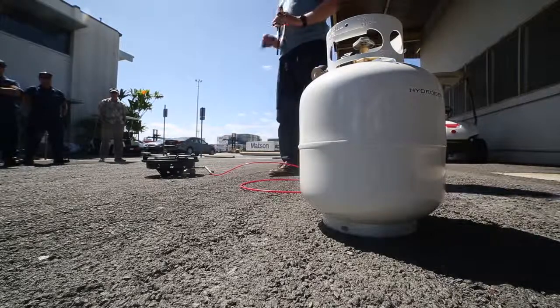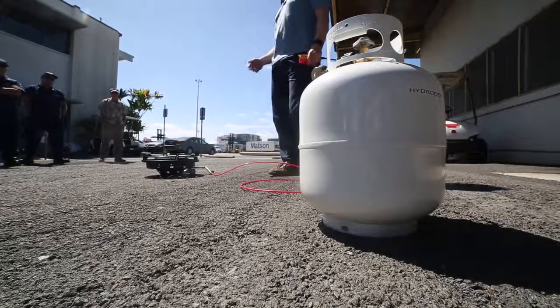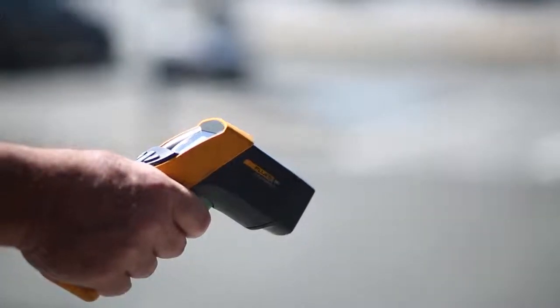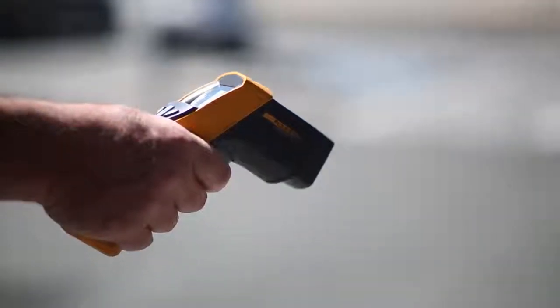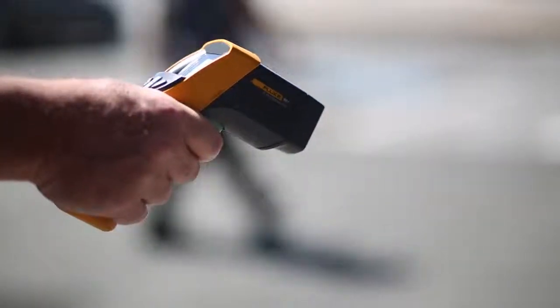You can see just a few little flecks of color, and that's mainly some impurities that are either in the line or on the burner itself. So in daylight, it's pretty hard to see. But that flame temperature, again, is about 4,000 degrees Fahrenheit, so it's really hot. Very little radiant heat, though, so if there's a jet of it, you can get very close to that, which can be a hazard. You know, there's not a lot of anything to indicate that you're getting into a hydrogen flame there. So, see that pretty well in the thermal imaging cameras?